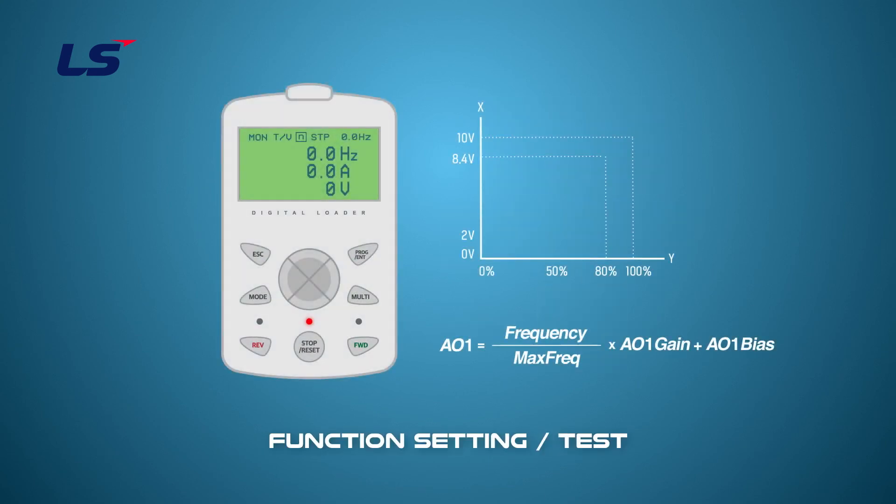We'll do an analog output test next time. Because bias is set to 20% and gain is set to 80%, the graph is drawn according to the output frequency as shown on the screen.